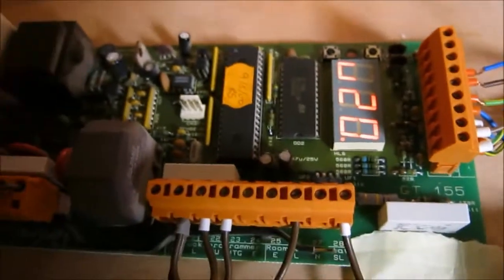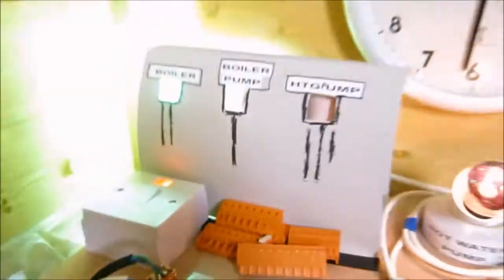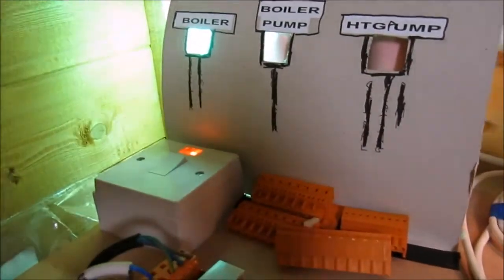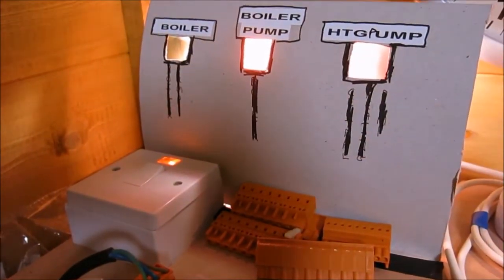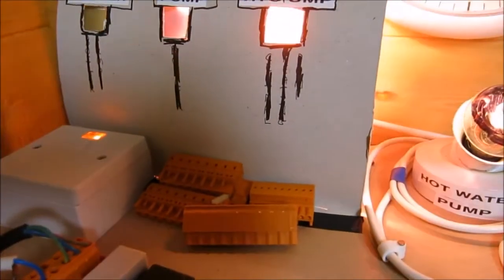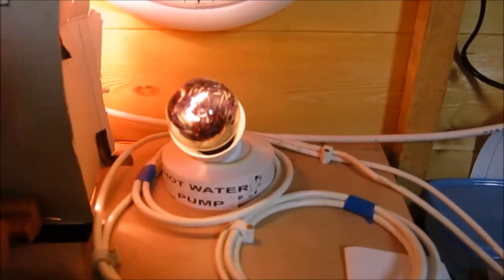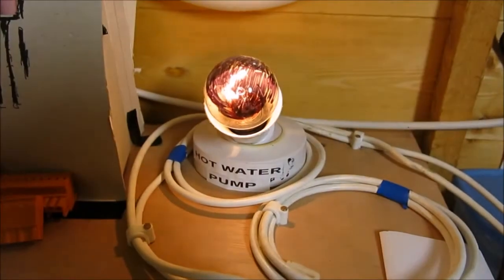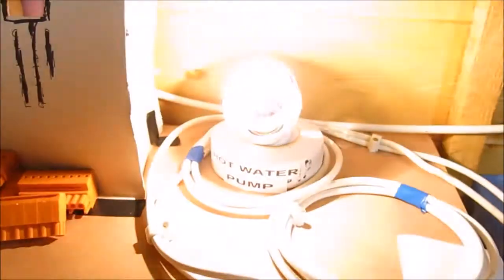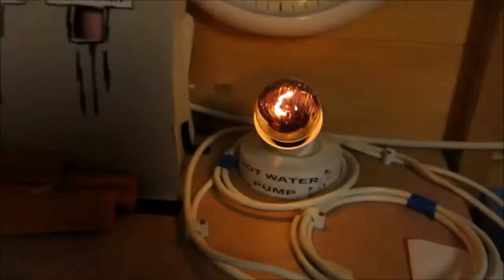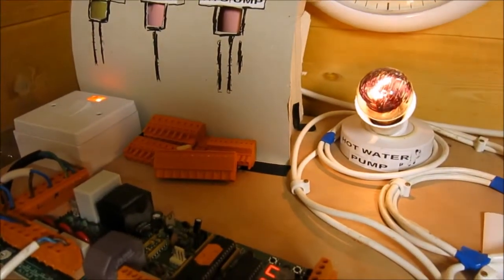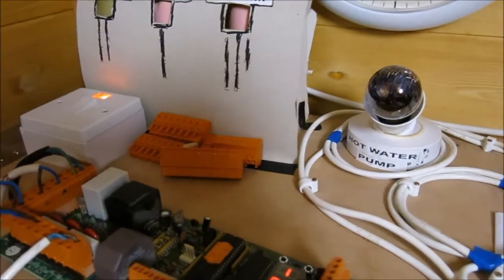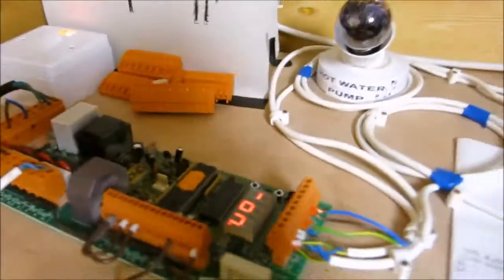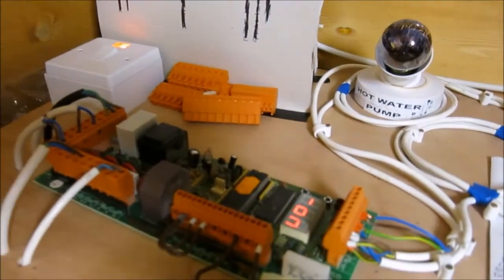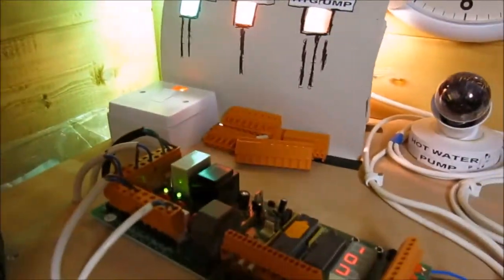Let go, and you get all the segments on the display, then the software version, version 20. Then it'll start to cycle through all the outputs - the boiler circulation pump, the heating pump. The direct hot water pump will be on low speed and it keeps flickering a little bit. In a second it'll go onto high speed and flicker like that. It'll do that a couple of times, then go off and back to normal. So that's the self-test on the older version 20 and below, and then we're back to normal running.